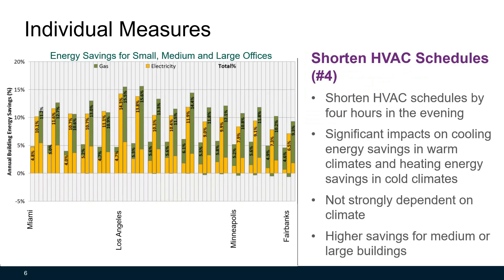The next individual measure is shortened HVAC schedules. In the simulation study, shortened HVAC schedules by four hours can save energy from 10 to 15 percent, with higher numbers for medium and large offices compared to small offices. There is a significant impact on cooling energy savings in warm climates and heating energy in cold climates. This is not strongly dependent on climate, and higher energy savings can be achieved for medium or large buildings.